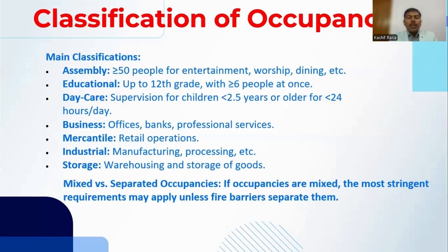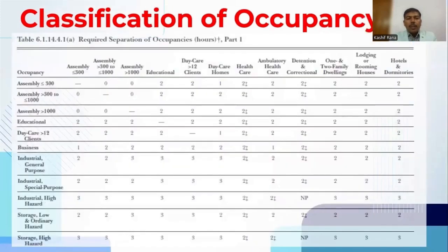If occupancies are mixed, then the most stringent requirements may apply unless fire barriers separate them. There is a required separation between different occupancies. We'll discuss one occupancy just as an example for more understanding. Business occupancy requires fire separation from assembly occupancy. If it is equal to or less than 300, then it requires 1 hour fire separation. And if there is educational occupancy just beside the business occupancy, then it requires 2 hour fire separation. Same like for industrial general purpose occupancy, it requires fire separation from assembly occupancy for 2 hours. And for educational occupancy, industrial occupancy requires 3 hour fire separation.